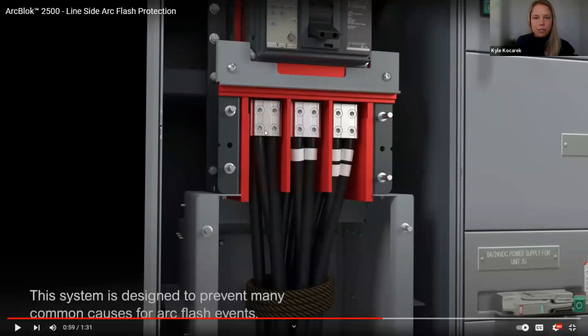The only place that an arc is forming is from lug to lug in this case. With the barriers at that distance, there's too much impedance. There's too large of a voltage drop from point A to point B. So that's a really, really weak, spindly arc. Plasma physics doesn't allow, at 480 volts, an arc to sustain longer than, I want to say, 2 or 2.5 inches.